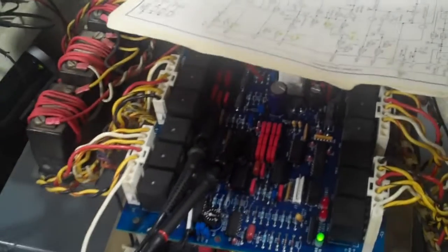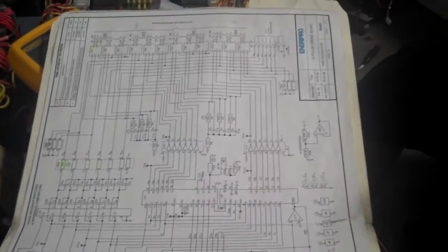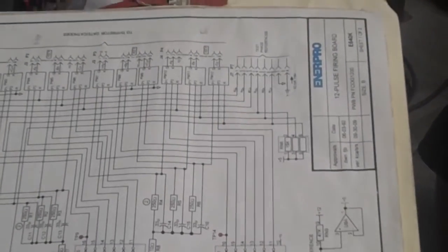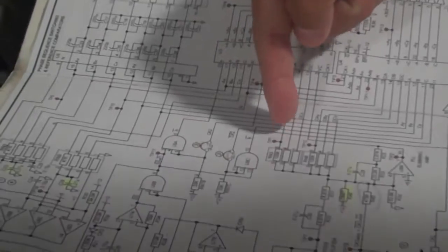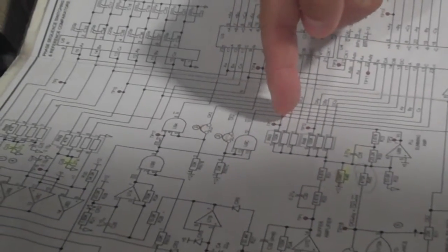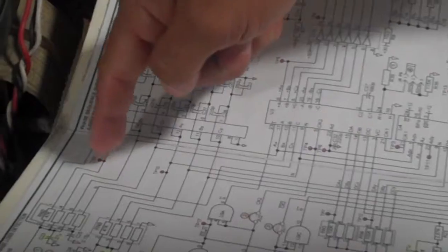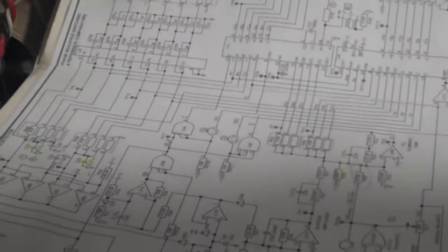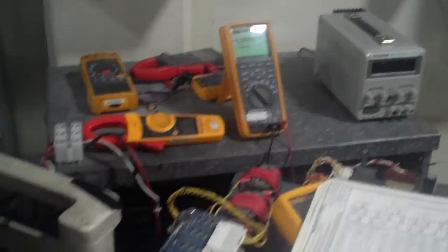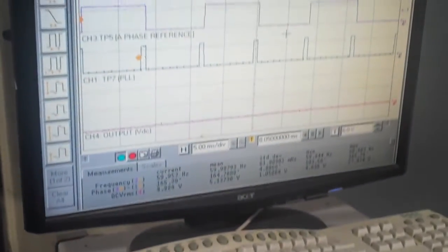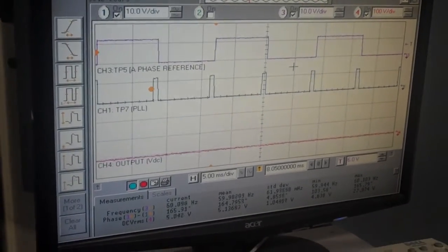Alright, today is July the 21st, 2020, Tuesday, and we're going to show on this, which will be our second video, TP7, the output of the delay angle command going into the LSI for the X bridge with respect to test point 5. Then we'll repeat the same thing for test point 10 and test point 12 for the Y bridge, while monitoring the output with a meter, with an oscilloscope, and also by looking at the value of SIG-high, the delay angle command, with this scope right here.